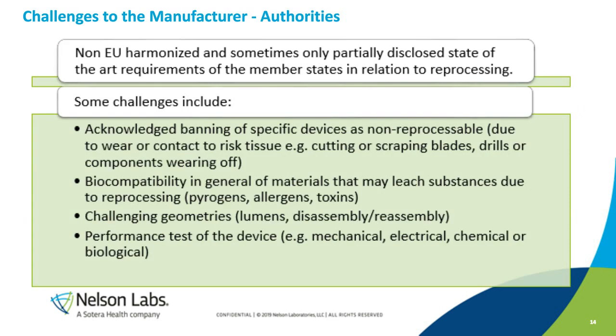Now I want to move into a few challenges that medical device manufacturers are now coming against. There are many reusable device processing parameters that are considered state-of-art requirements or only partially disclosed, so that this provides quite a challenge to medical device manufacturers. There are also some acknowledged banning of specific devices that have been deemed non-reprocessable due to wear or contact of risk tissue, for example, cutting and scraping blades, drills, or components that wear off. There are also issues with biocompatibility of materials that may leach substances due to reprocessing.